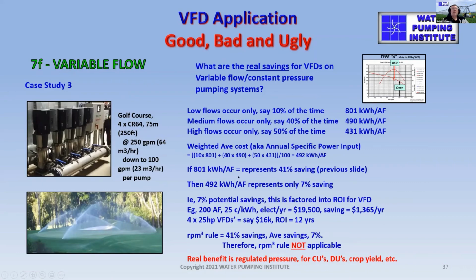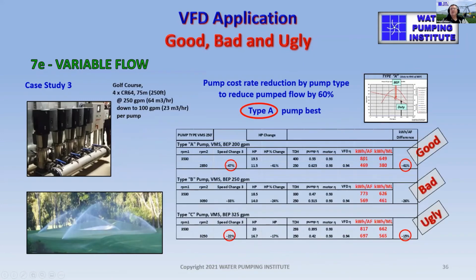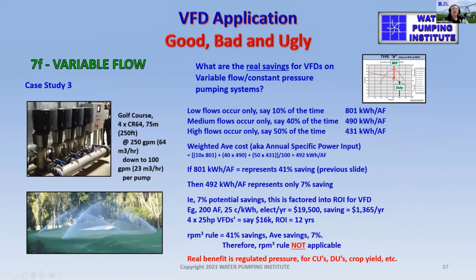Now, if we compare the energy savings at 801 acre feet, it represents 41% savings. So I'll just go back. So that's here. This is the good one, where the pump operating best saving scenario is from 801 to 469. It represents 41%. So if 801 kilowatt hours represents 41% saving, then 492 kilowatt hours represents only 7% saving. So 7% saving is all we're going to achieve on a VFD system on turf.